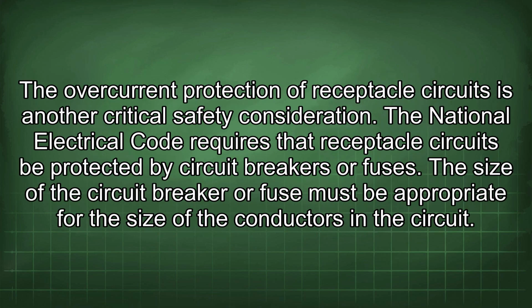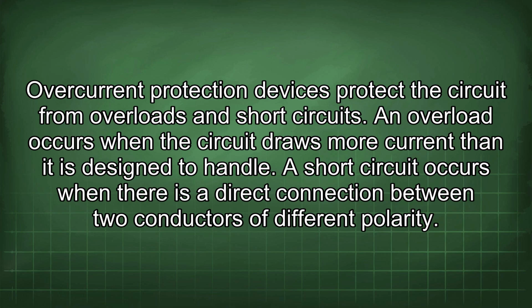The overcurrent protection of receptacle circuits is another critical safety consideration. The National Electrical Code requires that receptacle circuits be protected by circuit breakers or fuses. The size of the circuit breaker or fuse must be appropriate for the size of the conductors in the circuit. Overcurrent protection devices protect the circuit from overloads and short circuits.